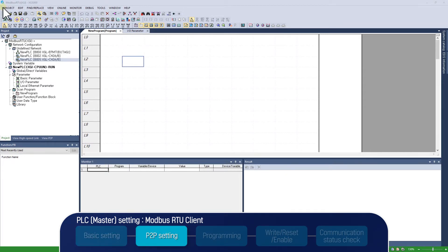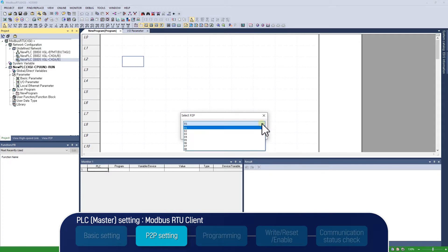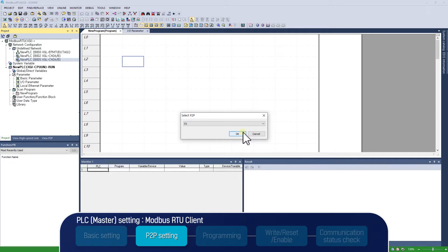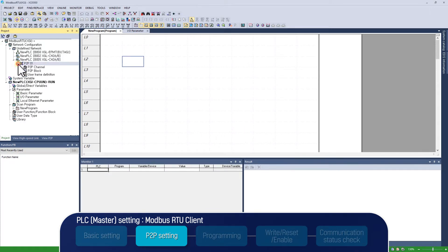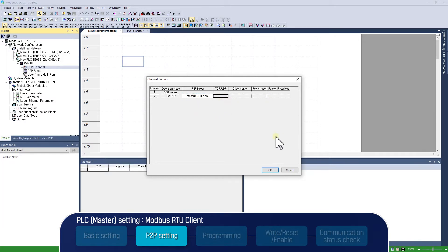For P2P setting, right-click on the CNET module under Network Configuration in Project Window and select Add Item P2P Communication, which pops up Select P2P Window, where you can choose unused P2P from 01 to 08. After adding P2P, you will find P2P Channel, P2P Block, and User Frame Definition in a row. Click P2P Channel and you will find Channel Setting window, where you could select Modbus RTU Client in P2P Driver.